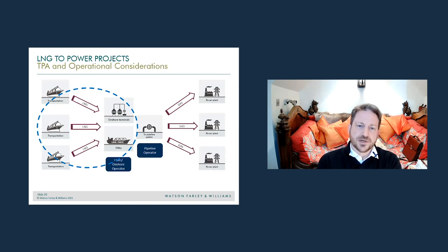of course, there's always a way of basically commingling your way out of an off-spec issue. And that may be whether it's too rich or too lean. If we're talking about the FSRU, then save for where you're getting a small-scale delivery, as Phil indicated, in most cases, the cargo lot that's being delivered will be similar, in fact, in many cases larger than the capacity of the FSRU. So that essentially rules out that means of mitigating.